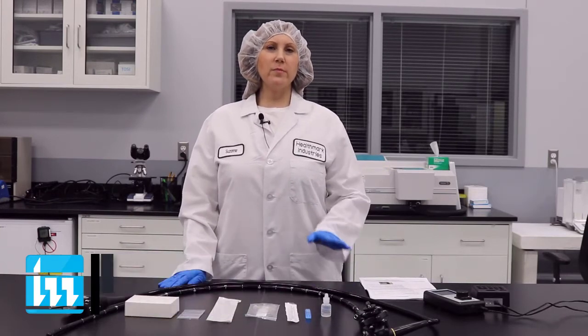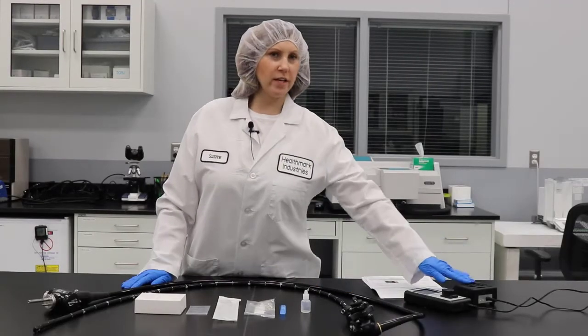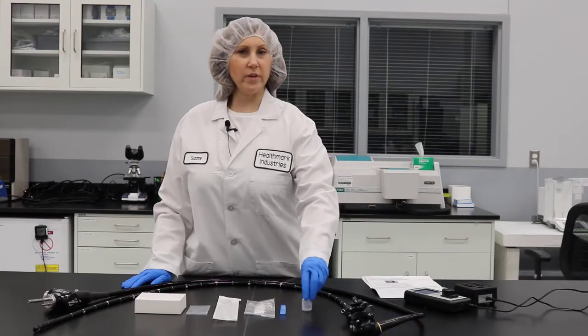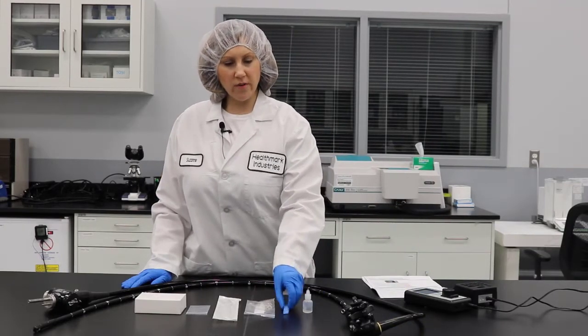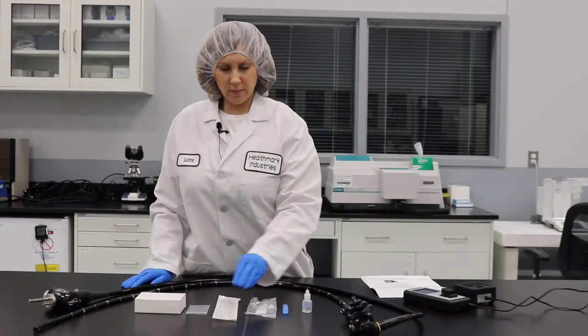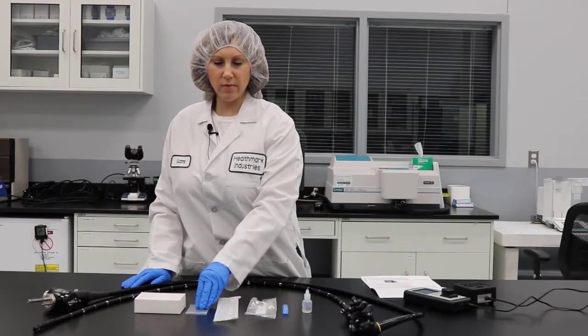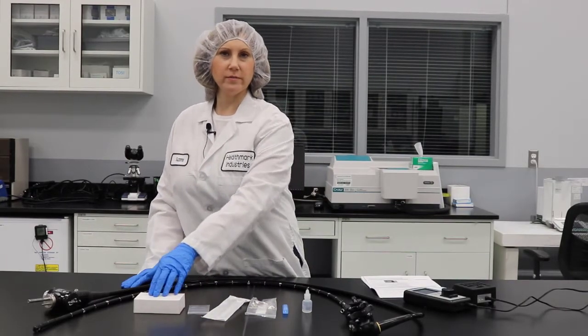Today we're going to go through the NOW test, and that consists of checking for gram-negative bacteria growth in flexible endoscopes after reprocessing. So the NOW test will consist of the incubator, the fluorometer, the reagent, the prepackaged water vials, a package of cuvettes, package of pipettes, Ziploc bags, and the cuvette holder.